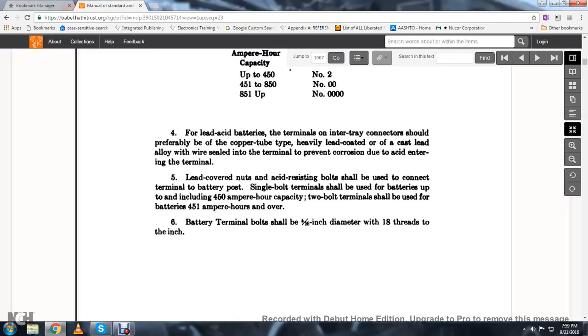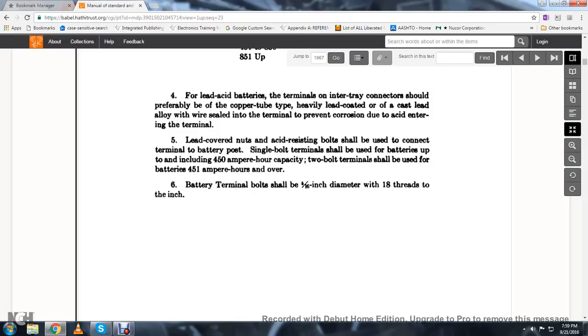For lead acid terminals, inter-tray connectors should preferably use a copper tube heavily coated with a lead alloy wire seal terminal to prevent corrosion due to acid entering the terminal. Lead-covered nuts and acid-resisting bolts should be used to connect the terminals to the battery post. Single bolt terminals should be used for batteries up to and including 450 ampere hours cell capacity. Two-bolt terminals should be used with batteries of 451 ampere hours and over.